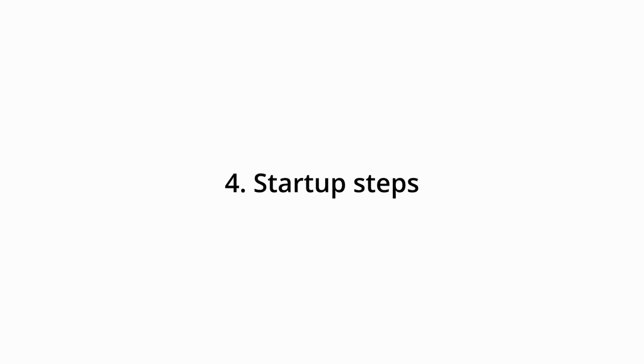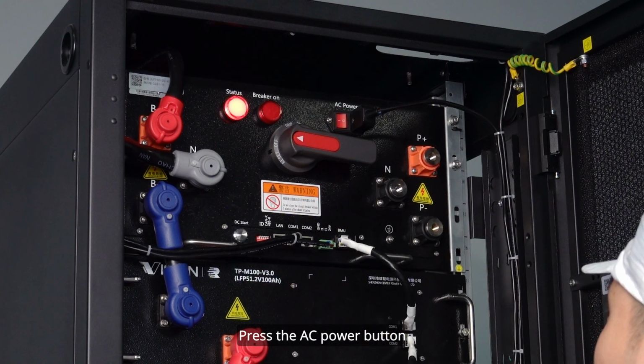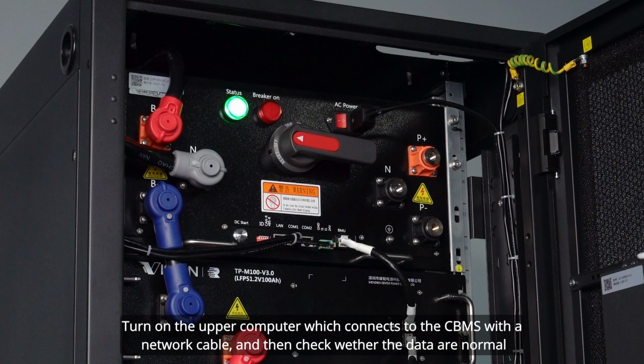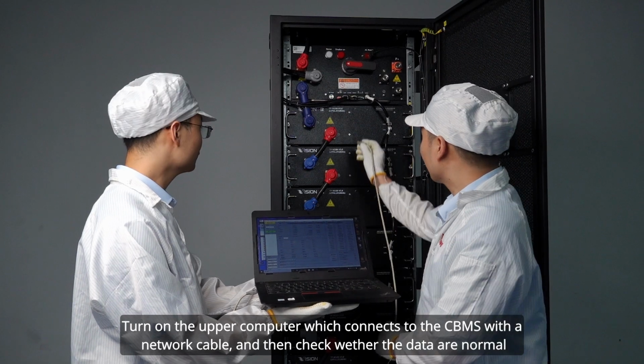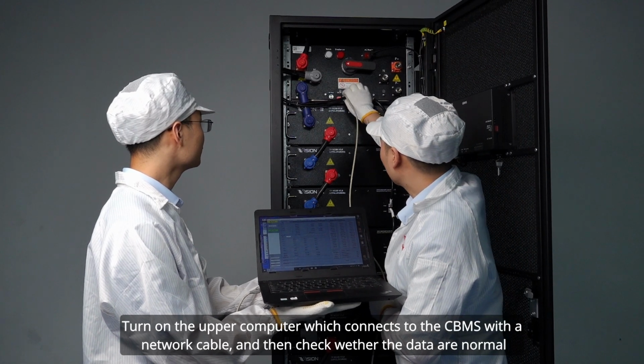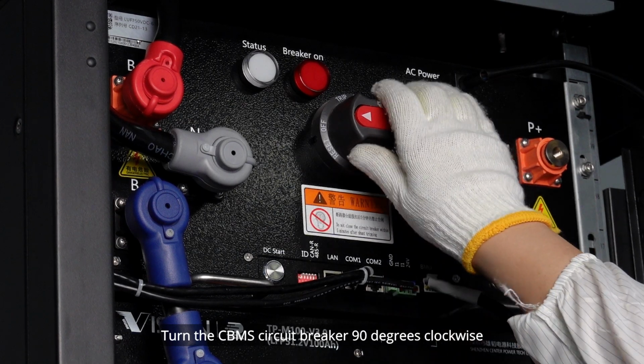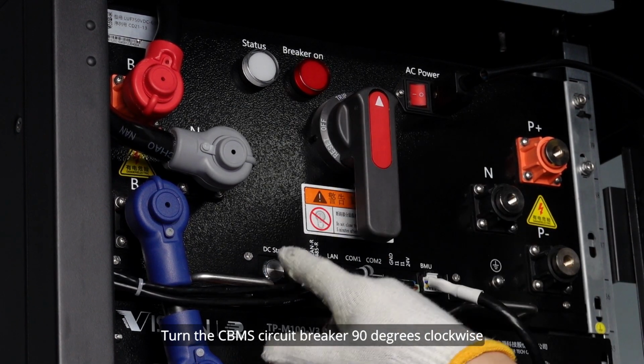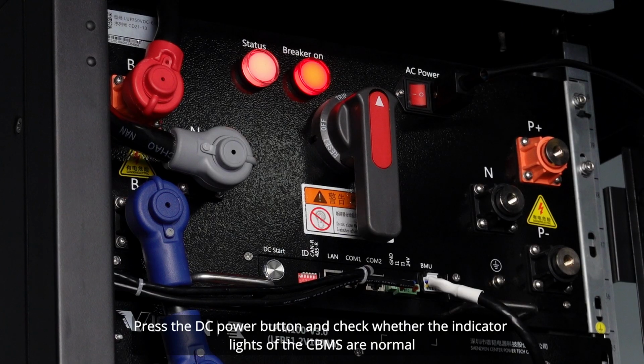4. Startup steps. Step 1. AC power supply testing. Press the AC power button. Turn on the upper computer which connects to the CBMS with a network cable, and then check whether the data are normal. Step 2. DC power supply testing. Turn the CBMS circuit breaker 90 degrees clockwise. Press the DC power button and check whether the indicator lights of the CBMS are normal.